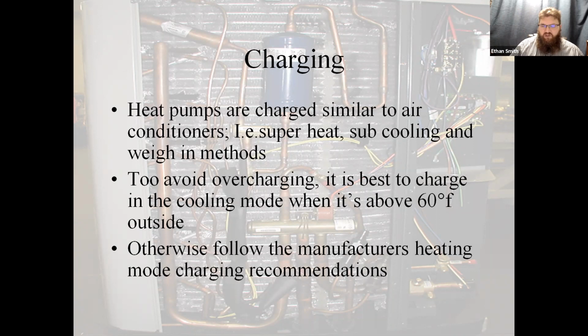So, heating mode charging procedures. On Trane, American Standard, and most other brands, they'll have a heating performance chart that gives you pressures, but they're almost always going to recommend that if you have to charge during the heating season, when you can't get an ambient above 60 degrees, you do a weigh-in charge for the outdoor unit, your line set length, and your indoor coil, and then come back in the spring and do a subcooling charge when you're above 60 degrees outdoor.